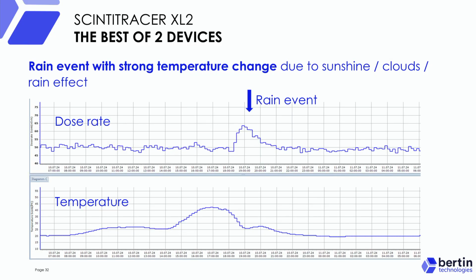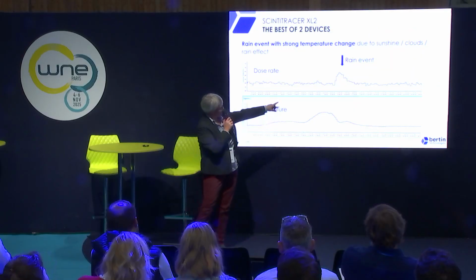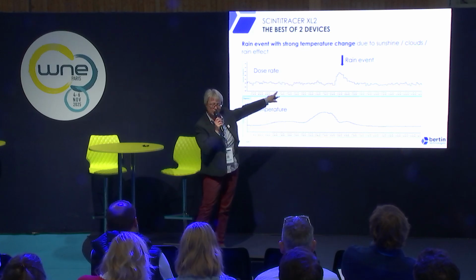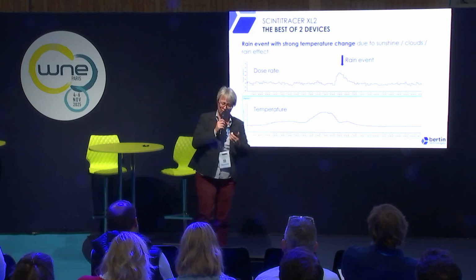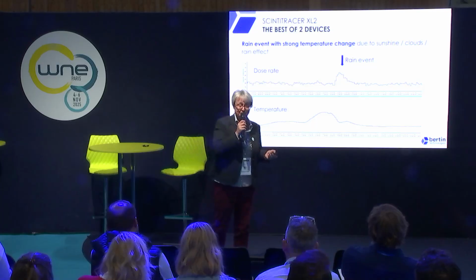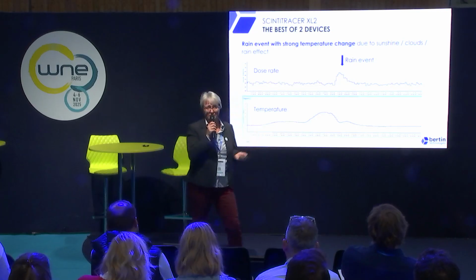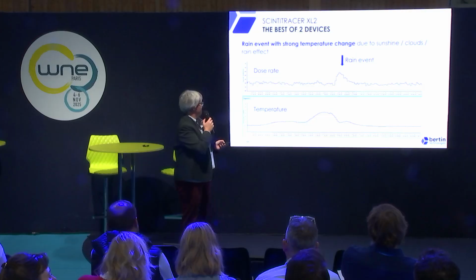Here is the installation, since a long time, on our roof in Frankfurt. We have very high temperatures. You can see that sometimes in Frankfurt it's more than 40 degrees or close to 40 degrees. And we have a drop in temperature, and this means that after this high temperature, we have heavy rain. You can see in the comparison that with the drop and the rain, the dose rate increases. And here, with the spectrometry, we could be sure that it is coming from rain and not from artificial radionuclides.